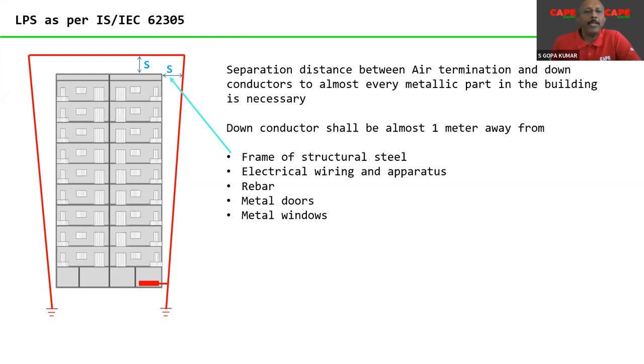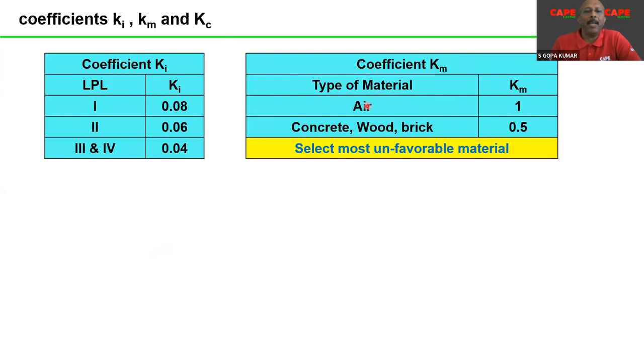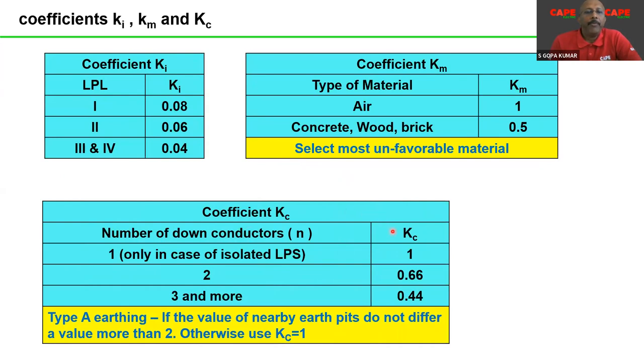Now, how is the separation distance calculated? There are constants, for example, depending upon the level of lightning protection, 1, 2, 3, 4; the constants are given in the standard. Depending upon the insulating material, air or concrete, wood or brick, the values are given. You always select the most unfavorable material. For example, in the next slides you will see how this has to be done. Then the coefficient, like the number of down conductors, one down conductor, two, three, and more, these constants are always given in the standard with some notes. Please have a serious look at that.